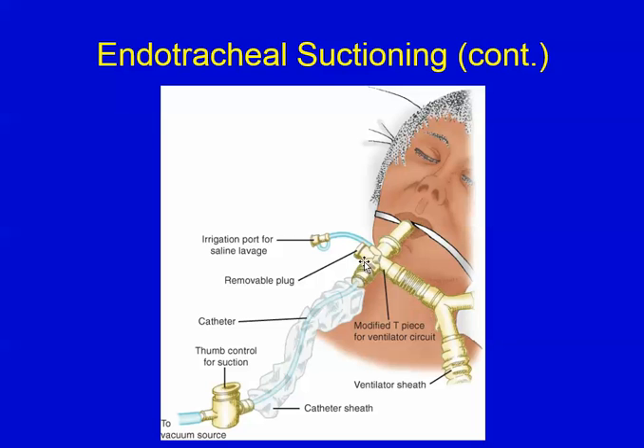All right, and so also with this type of suction catheter, many times you have condensation, or you have secretions that collect in the tubing here. Just to clean that out, that's what this removable plug is about. You just pop that off and it'll spray right out of there. Be careful not to get any of that on you. But that's one of the benefits of that plug there. There's another one too that we'll get to, but right now that's it.